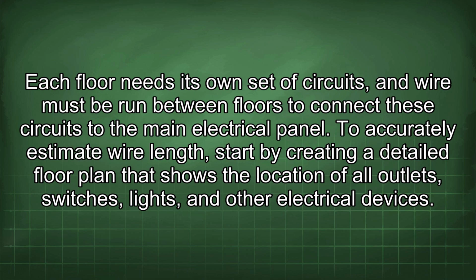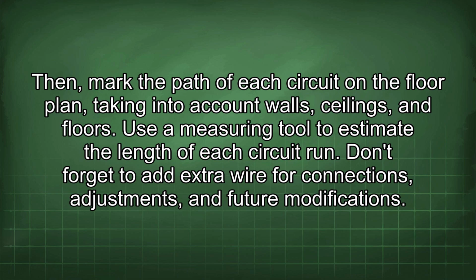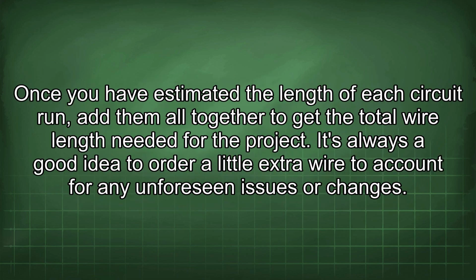the main electrical panel. To accurately estimate wire length, start by creating a detailed floor plan that shows the location of all outlets, switches, lights, and other electrical devices. Then mark the path of each circuit on the floor plan, taking into account walls, ceilings, and floors. Use a measuring tool to estimate the length of each circuit run. Don't forget to add extra wire for connections, adjustments, and future modifications. Once you have estimated the length of each circuit run, add them all together to get the total wire length needed for the project.